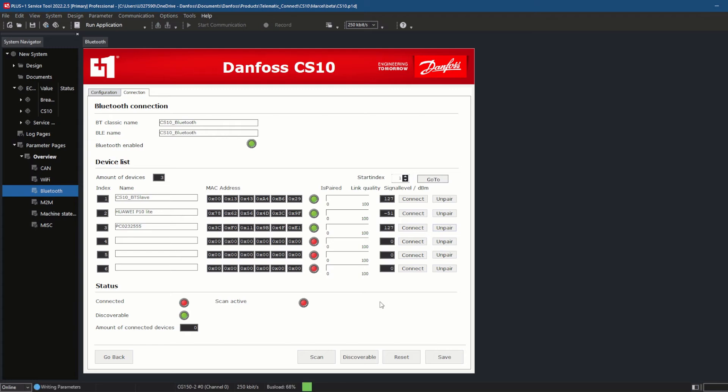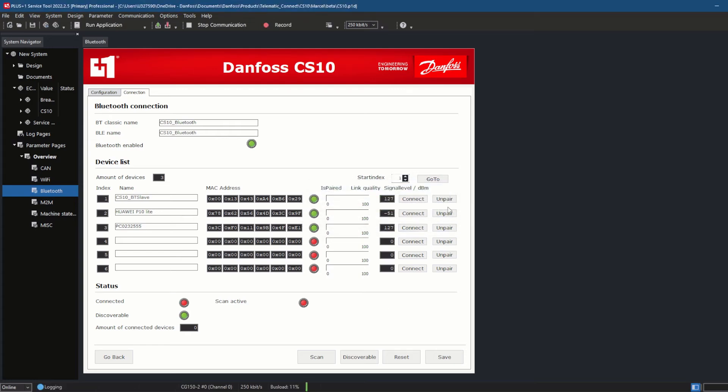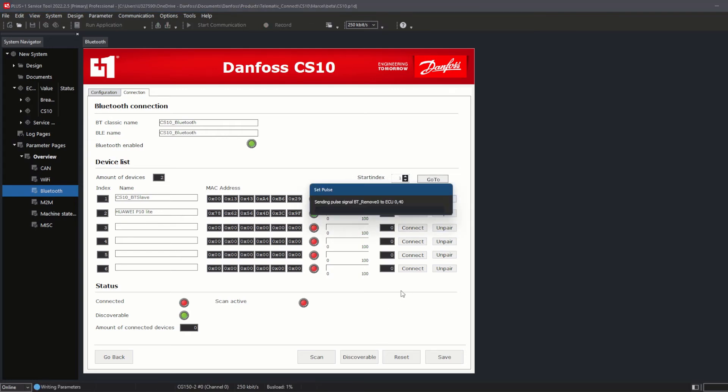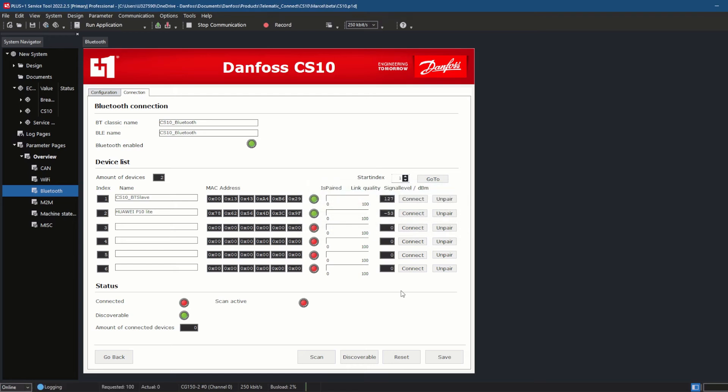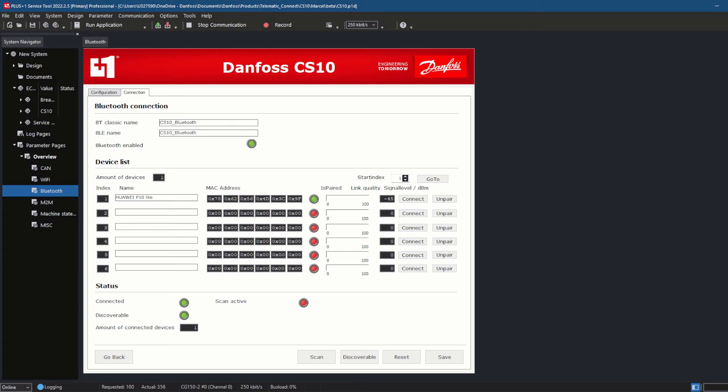My phone is now listed on the CS10 page Bluetooth connection under Device List. The is paired LED is green, which means that the pairing has successfully established. I clicked Connect to establish the Bluetooth communication between my mobile phone and the CS10. Once I did that, the LED Connected under Status changed from red to green. Now I can use my Mobile Service Tool app to connect to the CS10 for further servicing.